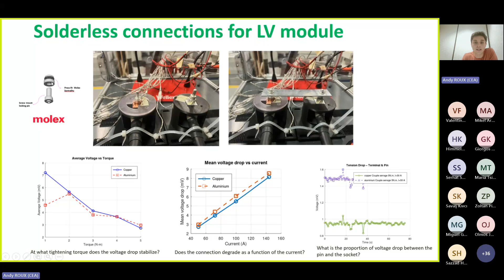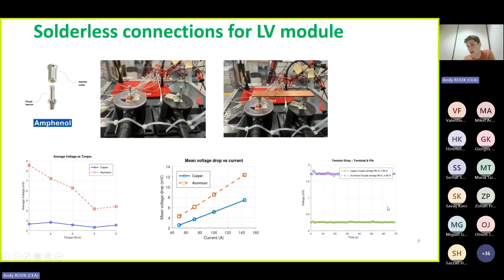We've done the same for the Amphenol solution. We have this graph that stabilizes at some point, and we also have a straight line, so it's not degrading as a function of current — we're good with this connection. We have the voltage drop to compare across solutions, and it's also 50-50 in terms of proportion of voltage drop on the connection.